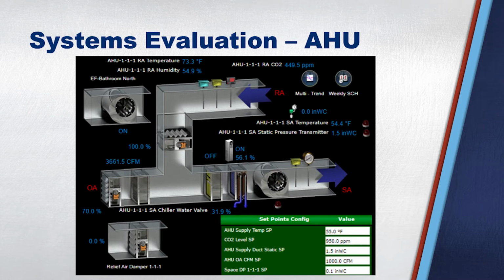So when you start to look at these, and color is bad, but so this is my airflow measuring station, and it's 3,600 CFM. And down on the bottom right is my outside air CFM set point of 1,000. My return damper is wide open. My outside air damper is where? Why am I over ventilating, or my airflow measuring station's out of calibration. But nothing's happening. It just sat there.